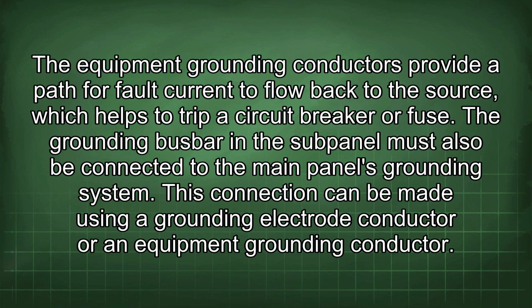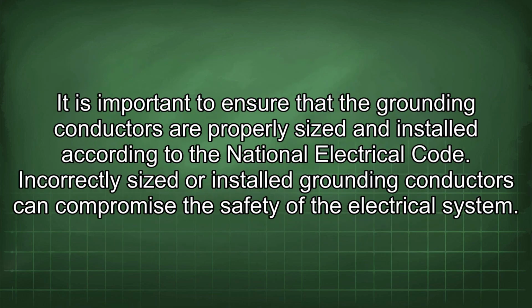The grounding busbar in the subpanel must also be connected to the main panel's grounding system. This connection can be made using a grounding electrode conductor or an equipment grounding conductor. It is important to ensure that the grounding conductors are properly sized and installed according to the National Electrical Code. Incorrectly sized or installed grounding conductors can compromise the safety of the electrical system.